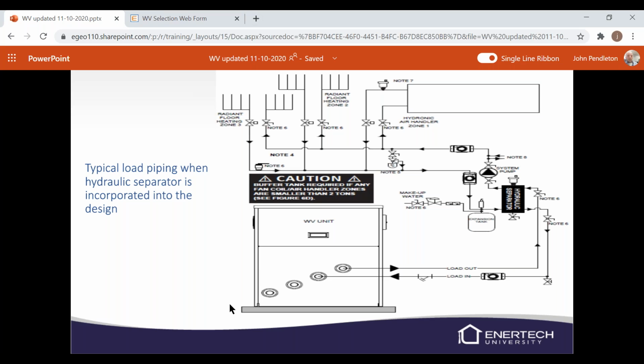And we found that we get micro bubbles and things, and they want to get stuck in the load pump that's in the WV unit. So it wants to lock out on flow, and we flush, and it's fine for a while, then gets more air in it. So with this setup, we're not as apt to go out on air in the system lockouts because it should be vented at different areas.